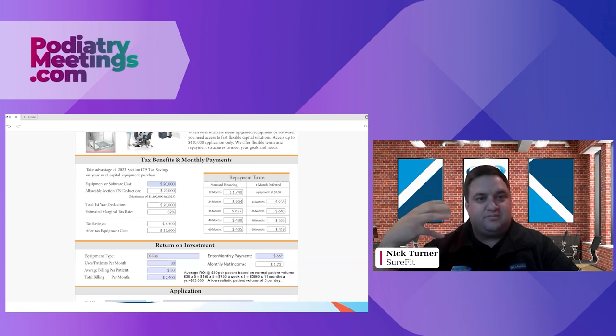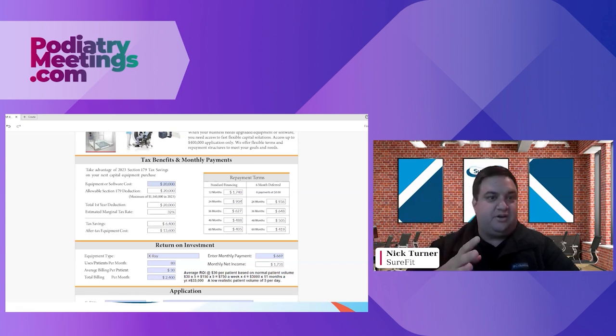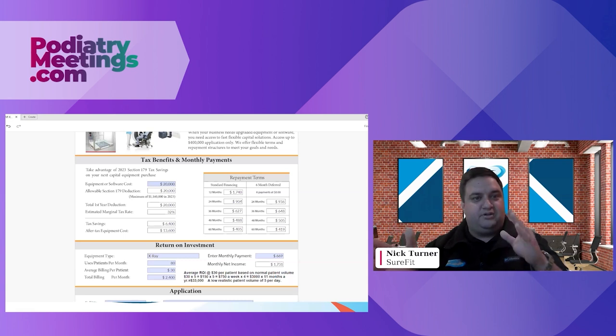With wireless panels, which is mostly what we recommend, they have the same thing as the portable X-ray, which is a battery and a battery charging. But when that battery is charging, you can't necessarily use the device at the same time, so you always have to have one in the cradle, one in use. If somebody uses it all day and doesn't charge either battery, the next day you're going to have a dead unit. That's the biggest issue with portable.